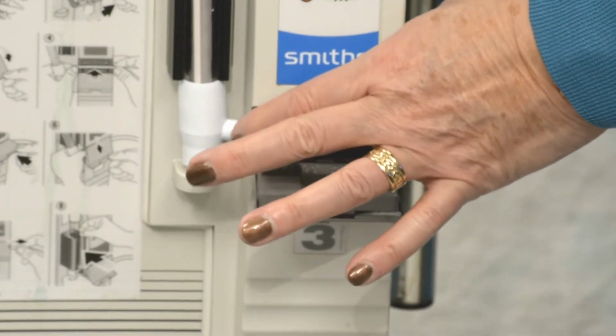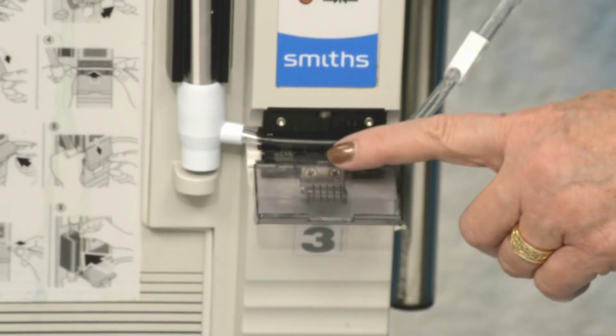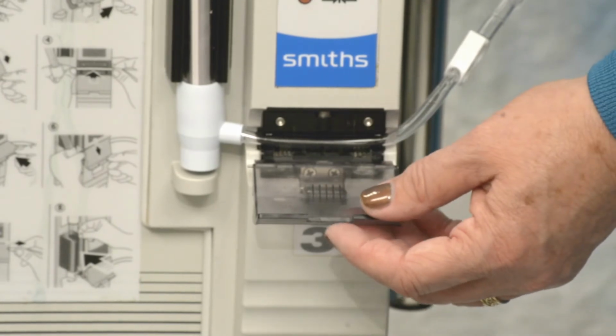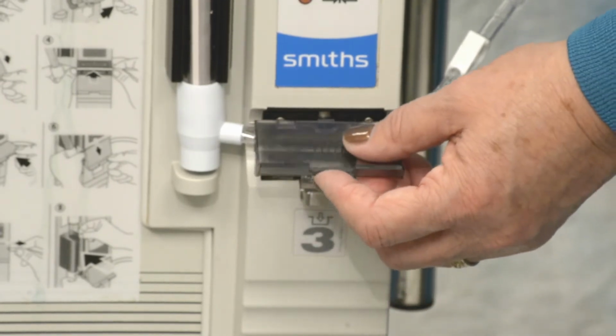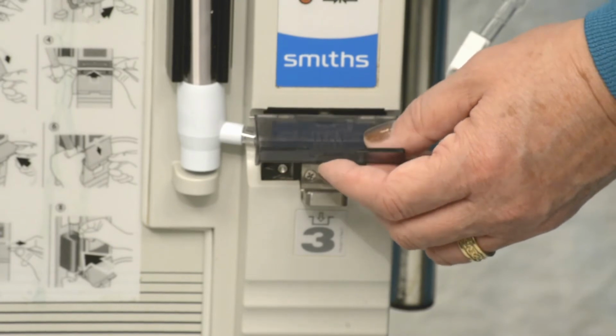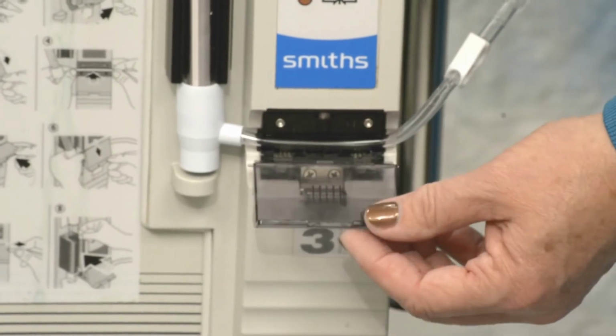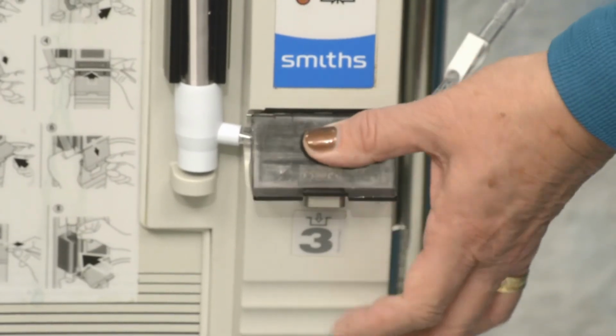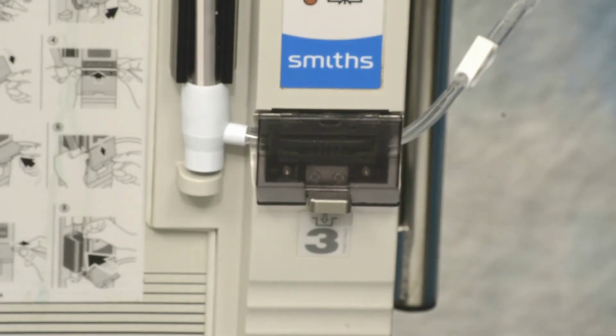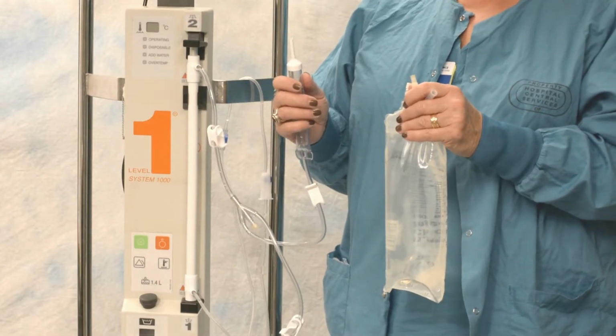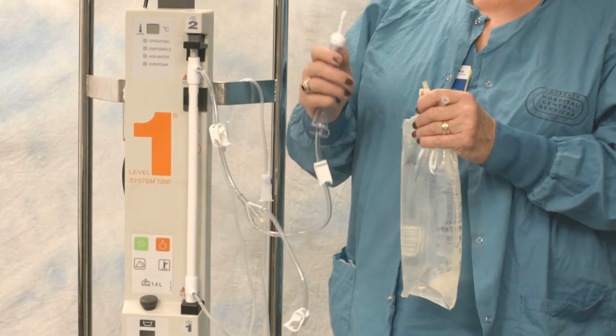Notice on the door that there's a little tab. That tab must be firmly seated in the top part of the tubing holder before you can close the door. Lift the door up, seating the tab, then push the door down until it clicks into the door holder. After inserting the tubing into the machine, you're ready to spike your bag.